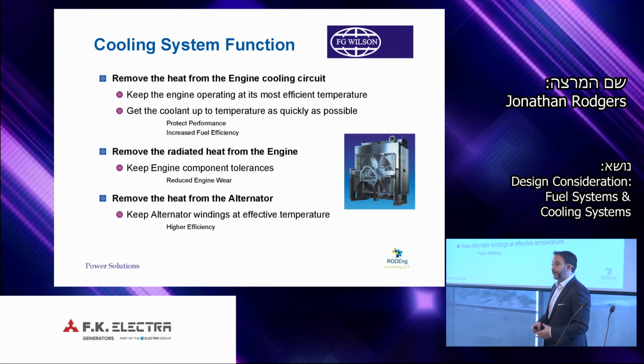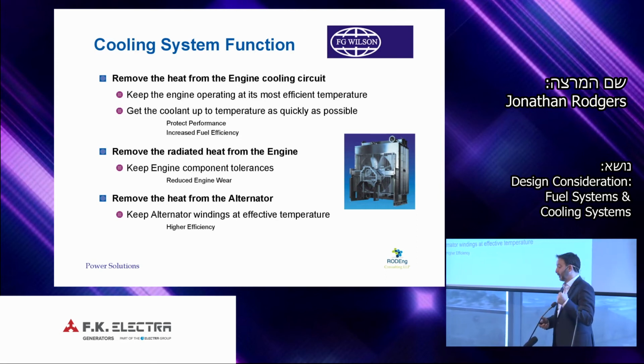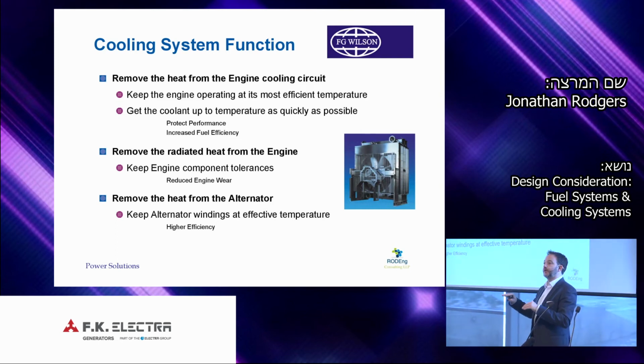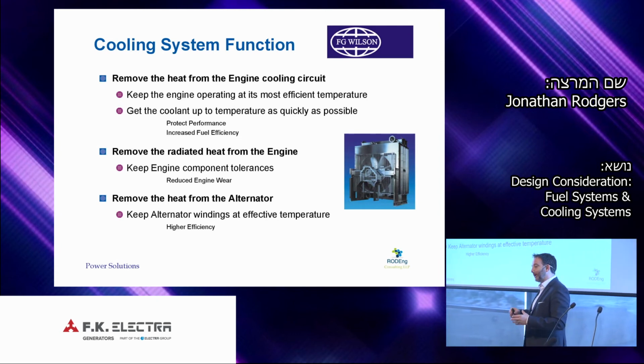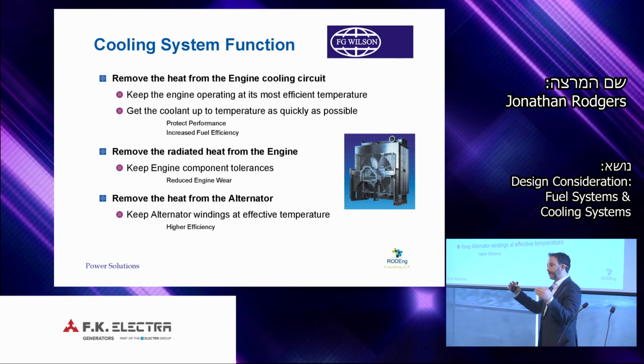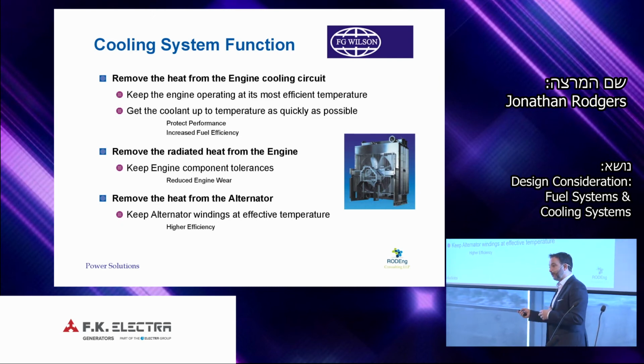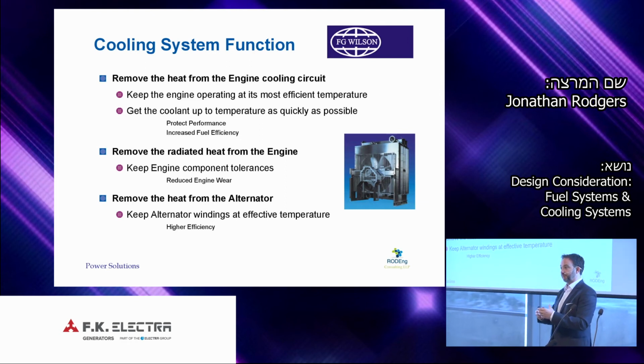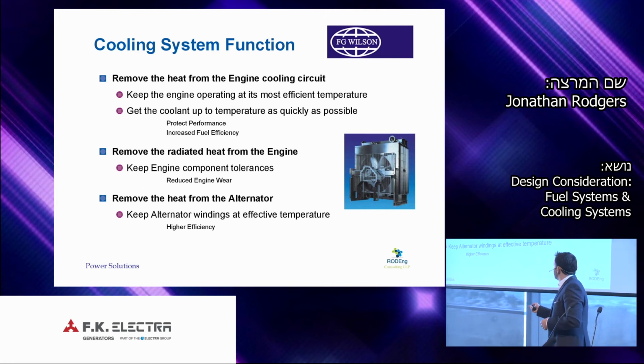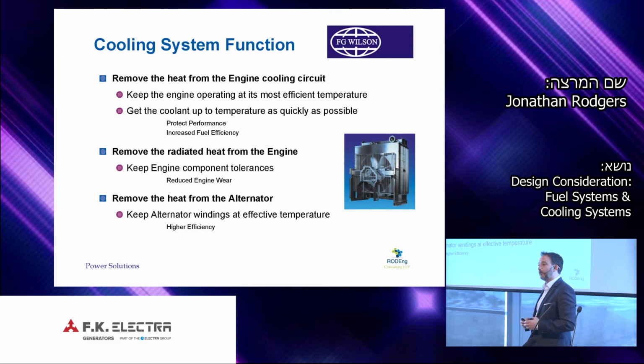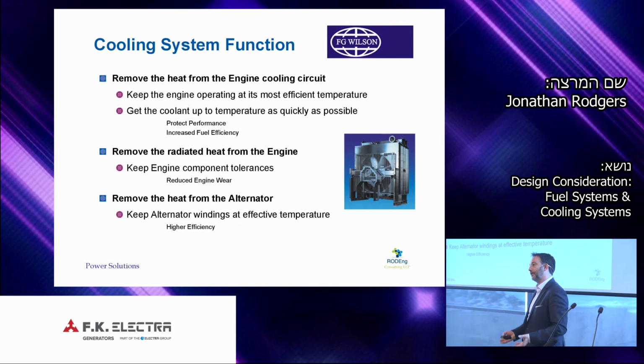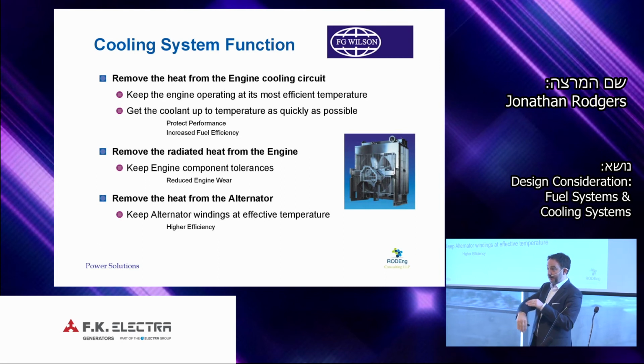So the main function of the cooling system is to remove heat from the engine. This is to keep the engine operating at its optimum, most efficient condition. One part of the cooling system is also to heat the engine up as quickly as possible. So we have thermostatic valves, we have control valves to keep heat in the engine when it's starting up or on low load. We need to keep the engine at high temperature to maintain efficiency and reduce engine wear. So when we have the engine up on high load and to temperature, we then need to remove the heat to keep the tolerance of all the moving components. And this is to reduce engine wear. So we also must remove the heat from the alternator and the alternator windings to maintain the efficiency of the alternator. If the alternator becomes too hot, then efficiency drops off dramatically, significantly.